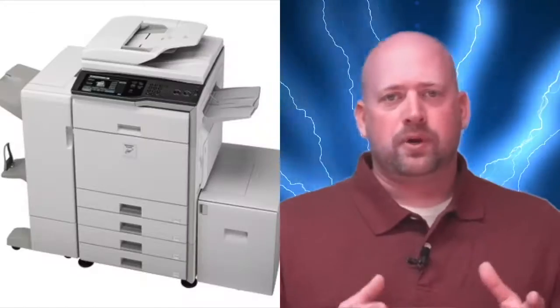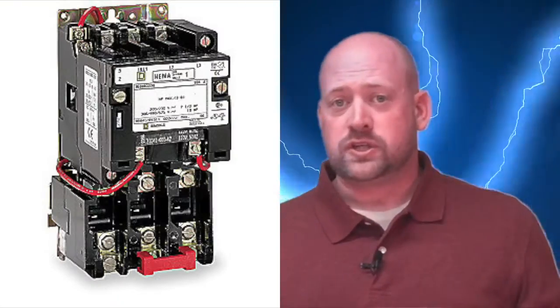So where do transients come from? Now, lightning always comes to mind as the main transient cause. However, there are a lot of other devices that can induce transients onto a circuit, many of which are internal to a facility. Now, these devices range from copiers, coffee makers, vacuum cleaners, VFDs, motor switching, and ballast, just to name a few. It's estimated that 80% of transient activity at a given facility is internally generated, and transient activity is believed to account for 80% of all electrically related downtime.